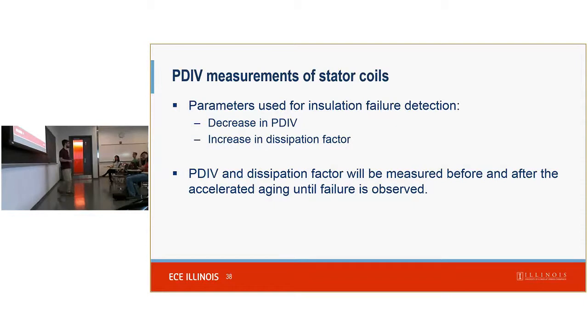Another part of the winding qualification is partial discharge inception voltage measurement of the stator coils. PDIV is how we abbreviate that. That indicates when you have an insulation material, if you have wires next to each other, if there are defects or air bubbles within that insulation, you can get voltage discharge or tiny little electric arcs within the insulation. So it's not a full discharge from one conductor to the next. It's small ones within the insulation. And this is not an immediate huge problem during operation. It's not going to immediately destroy it, but it is a lifetime concern, because each time there is this partial discharge, it's going to damage and wear away more of the insulation.